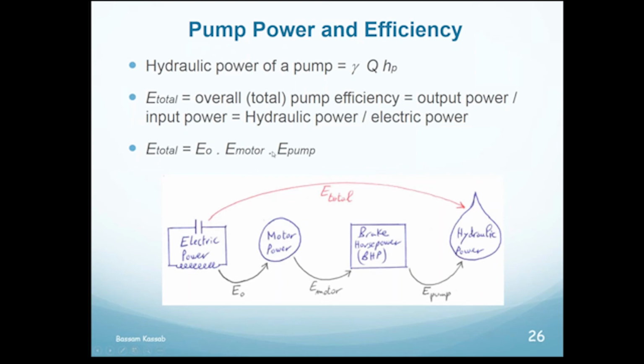You do not add those efficiencies because you end up with a number larger than 1. You have to multiply them. The E-motor efficiency, for example, is the brake horsepower over the motor power, always output over input. The arrow that I drew here represents the direction of flow, of power movement.